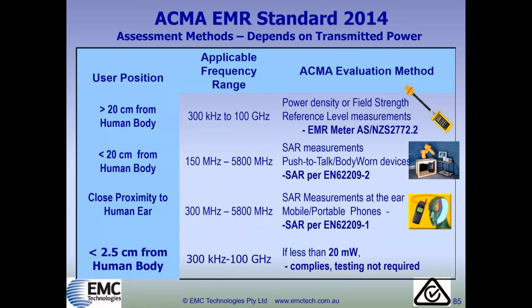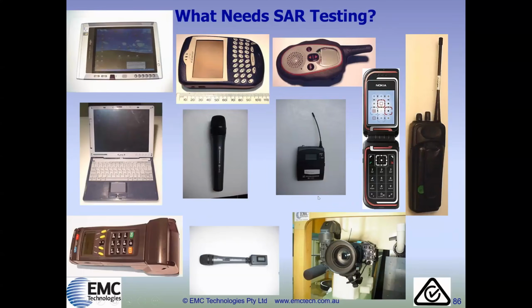Now this table essentially summarises the ACMA EMR standard 2014 and how you assess against it. If the device is less than 2.5 centimetres from the body and less than 20 milliwatts, then there's no further assessment required, and you can presume compliance without any tests whatsoever. If it's used within 20 centimetres of the body, you've either got to make an SAR measurement, use calculations, or use field strength measurement with the meter. I must update this slide.